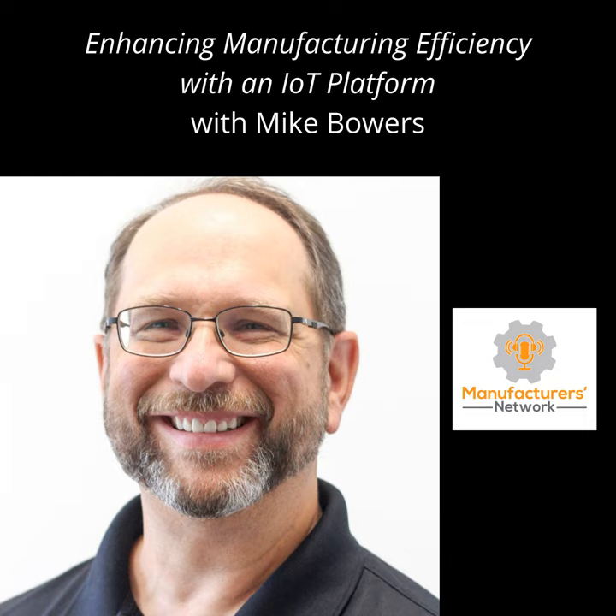What we do in our product is create drivers that can talk to the Siemens protocols or the Allen Bradley protocols. The industry, knowing this is a real problem with proprietary protocols that lock you into a vendor and make it hard and expensive to get data out, developed more open-ended protocols. Modbus, for example, is pretty open-ended. It's still down at the bit level where you're tweaking what this bit means and what this number means, but it's not proprietary.